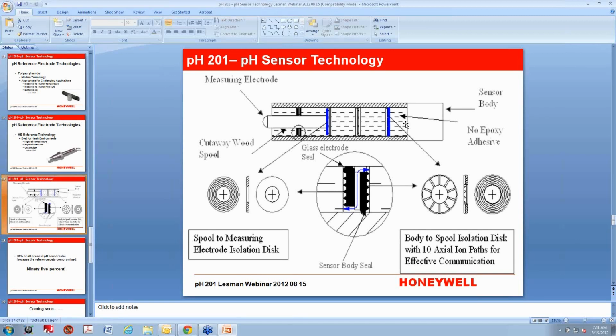And we put in our HB test sensor, which was the test sensor at the time, and I know this is hard to believe, but it was installed for over 9 months and still running when I last checked on it. I think they ended up giving it the heave-ho somewhere around 12 months. So we went from the best we could get out of a gel reference, 6 weeks with the DuraFet, to 12 months. So that's pretty awesome. It's really great technology. These devices currently come with a glass measuring electrode.